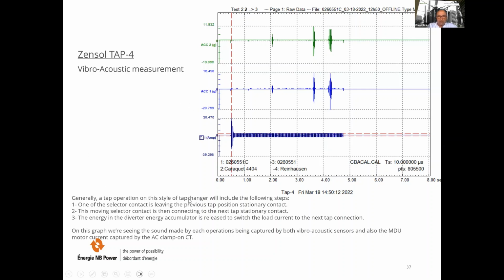Generally, tap operation on this style of tap changer will include the following steps. One of the selector contacts is leaving the previous tap position stationary contact. This moving selector contact is then connecting to the next tap stationary contact, and the energy in the diverter energy accumulator is released to switch the load current to the next tap connection. On this graph, we are seeing the sound made by each operation being captured by both vibroacoustic sensors and also the MDU motor current captured by the AC clamp-on CT. This is the motor current, and here the accelerometer 1 and accelerometer 2. In fact, we need only 1, but in this case, they have preferred to use 2.